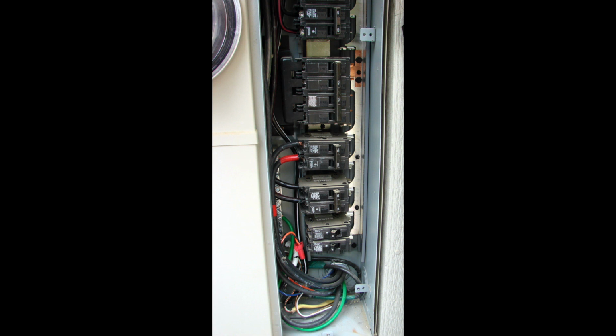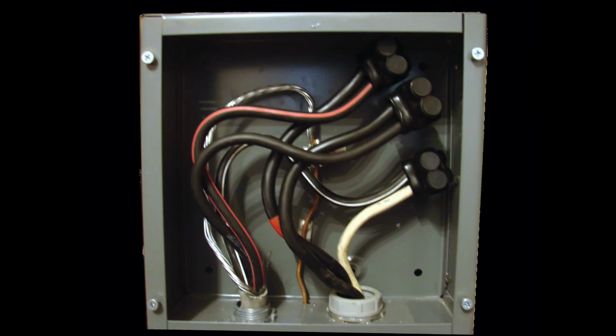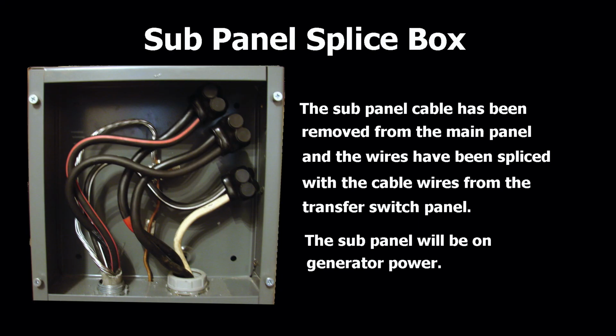we've pulled back the wiring from the other sub panel that is fed off of the main panel. And again, this is going to be a second sub panel that will be on generator power. But instead of feeding it from the main panel, we are feeding it through the generator panel. It doesn't have a lot of circuits on it, mainly lights and receptacles. But we brought the wires out of the main panel and we're splicing them in an exterior junction box. And so this junction box, the sub-panel cable has been removed from the main panel, and the wires have been spliced with the cable wires from the transfer switch panel.